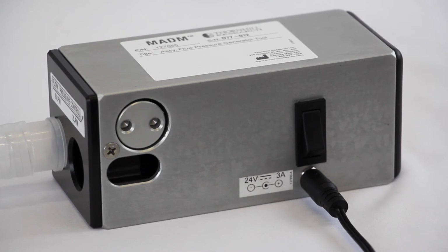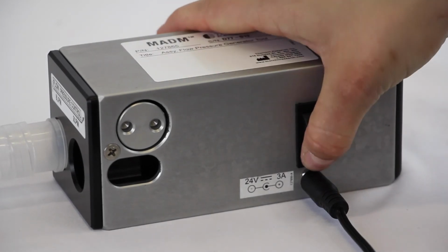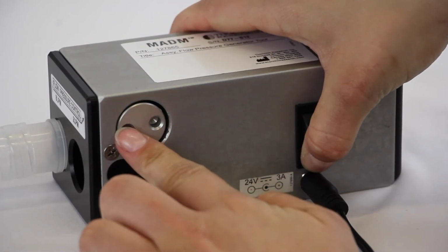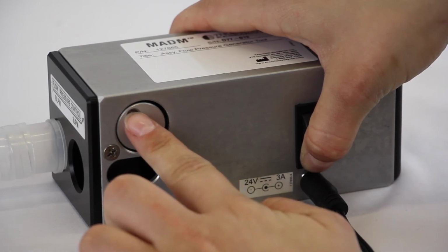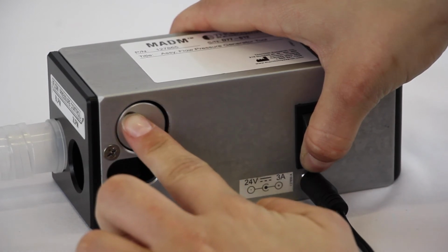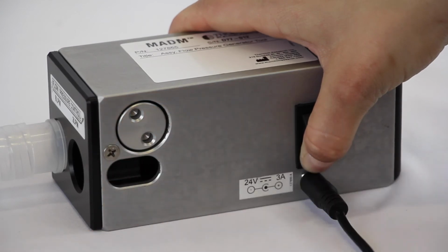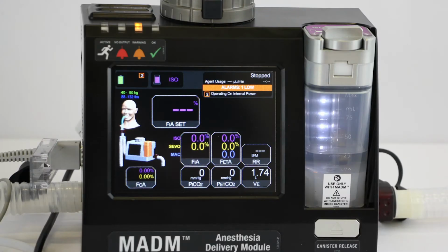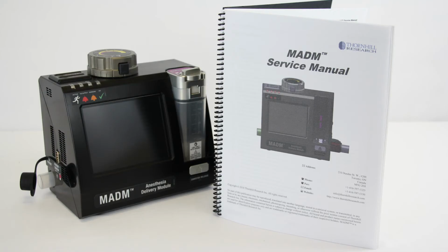First, check the flow accuracy using the adjustable flow source. Press and hold the activation switch on the adjustable flow source and use the control dial to adjust the speed until the flow meter reads a flow of 1.5 to 2.5 liters per minute. Ensure that the minute ventilation indicated on the MADM main screen is within 10% of the value measured by the external flow meter. If the values differ by more than 10%, repeat the pressure leak test. Otherwise, refer to the MADM service manual or contact Thornhill Medical for support.